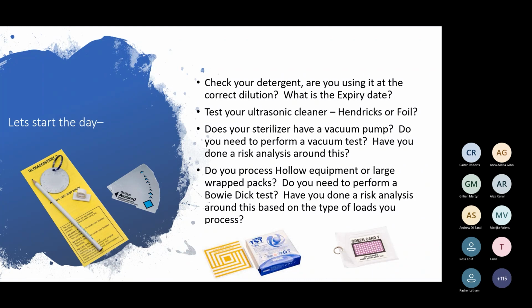Are you going to use Hendricks or Foil? If you're going to use foil in your ultrasonic cleaner, the correct procedure is to fill up your ultrasonic. You put in your detergent, you degas it, then you put in your foil. Now, to put in your foil, as per the ultrasonic Australian standard, you have to suspend 3 sheets of foil in the tank of your ultrasonic. So you have to have 3 pieces of wire or something across the top, or a wooden skewer or something. I don't know what it is, but you would then hook your aluminium foil over those 3 suspension devices.